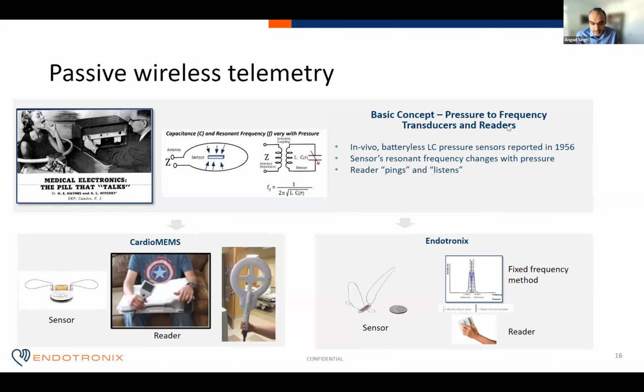So this passive wireless scheme at a very high level consists of a passive LC tank circuit, so an inductor-capacitor tank circuit. And you can tailor that circuit so that the capacitance changes as a function of pressure, and that results in a frequency change. So these circuits have a resonant frequency. The resonant frequency changes as a result of pressure changes, and that can be picked up by an external reader, which also has a coil that couples to the coil on the implant circuit. And so this basic concept was adopted by CardioMEMS. And the pictures I've shown you are the real world version of that electrical circuit for an implantable system.